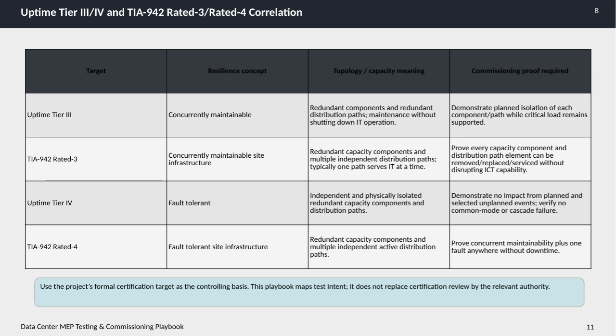TIA 942 rated 3 aligns closely with this concept, but specifically refers to concurrently maintainable site infrastructure. It requires redundant capacity components and multiple independent distribution paths, though typically only one path serves IT equipment at a time. The commissioning proof involves showing that every component and distribution element can be removed or serviced without disrupting ICT functionality. Moving to Uptime Tier 4, the standard steps up to fault tolerance.